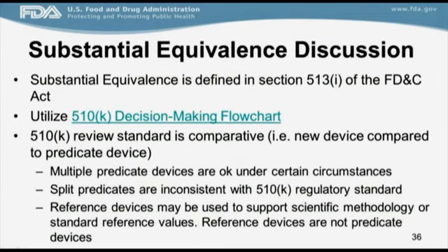Within your 510K, you also want to include a detailed substantial equivalence discussion. The substantial equivalence discussion is the foundation of your 510K. So please refer back to the 510K decision-making flowchart and go through each of those decision points so that you are clear and the reviewer is clear as to how you are demonstrating substantial equivalence. The 510K review standard is, again, comparative. So you're comparing your new device to your predicate device.